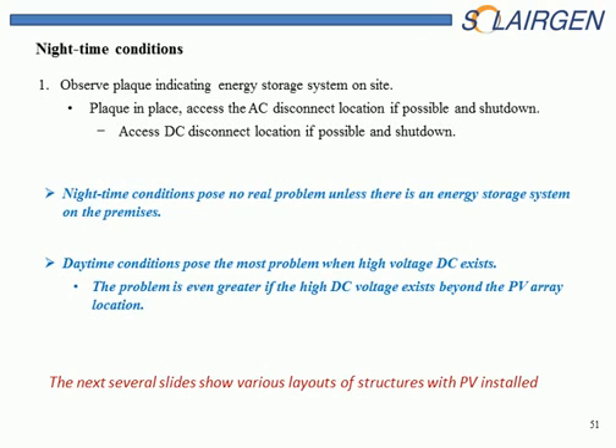Nighttime conditions seem to be safe since there's no PV system working, there's no DC potential outside. However, there is the possibility that there could be an energy storage system on site. So look for the plaques to see if there's an energy storage system. If you don't see any AC or DC disconnects outside, but you do see a PV system, that's a pretty good indication that there's an energy storage system, because the utility would require an AC disconnect outside, and if there's not one, then they don't know about the system, and more than likely it's an energy storage system that's in violation of all these code requirements.